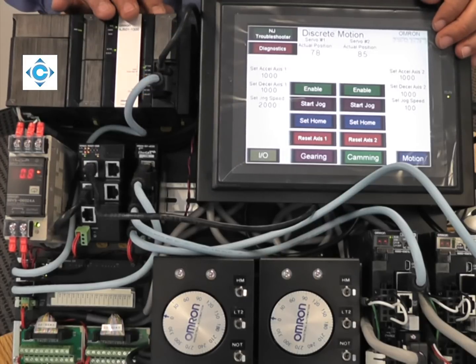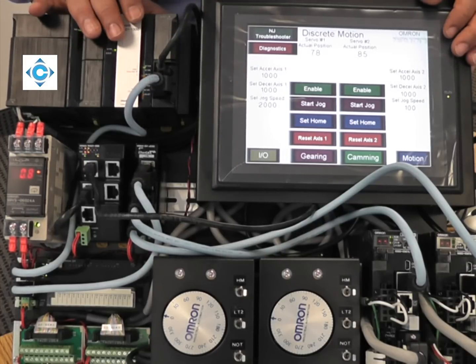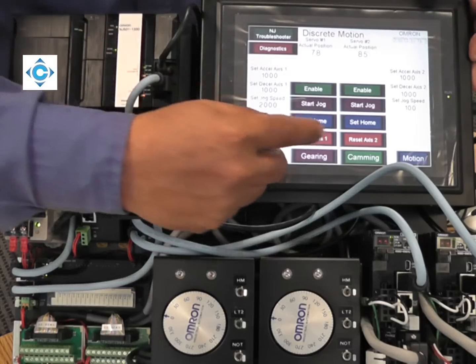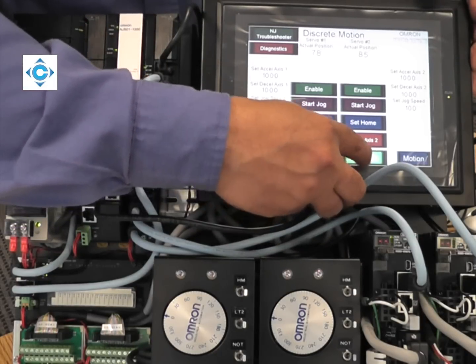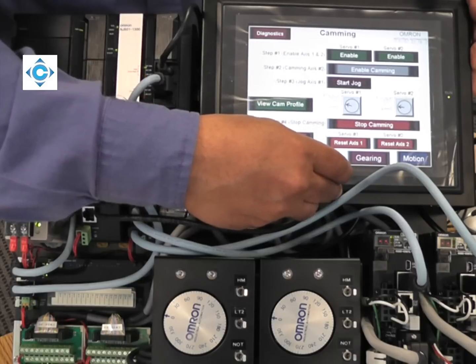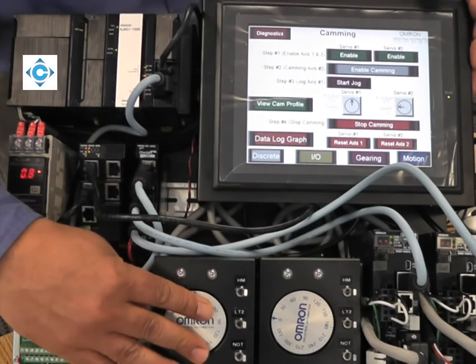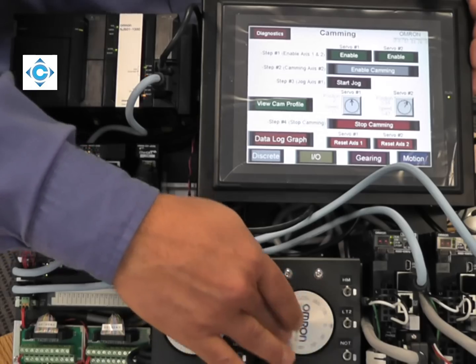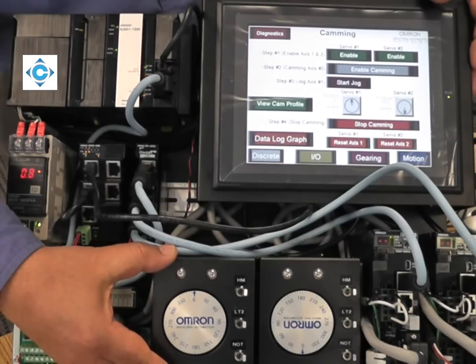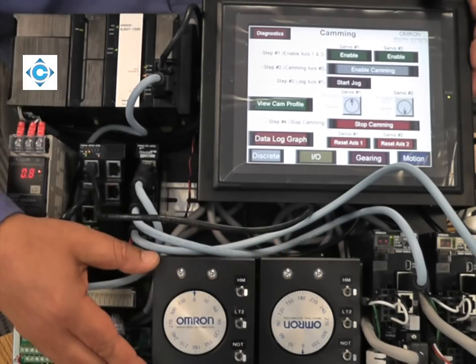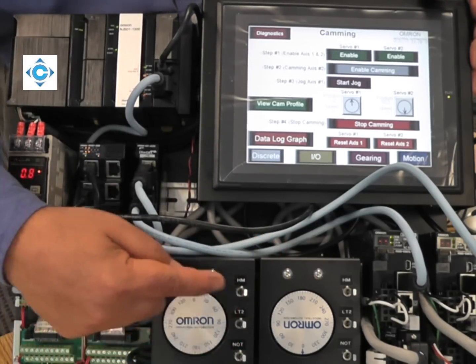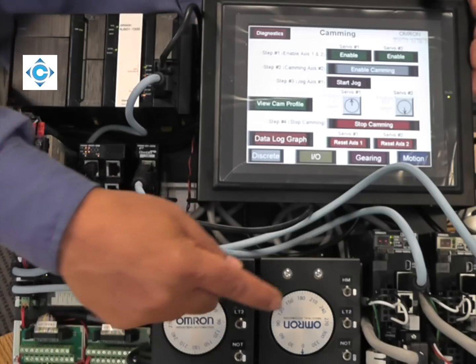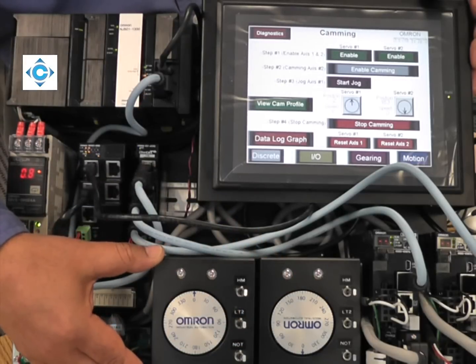The second one I want to show is camming. I go to the camming screen. We have a simple profile where, again, this first axis will be the master. The second axis is the slave. But every time the master makes 720 degrees or two revolutions, the slave will make only 360 degrees.